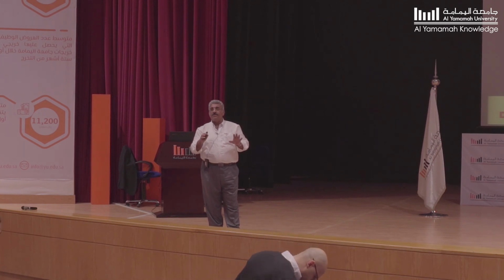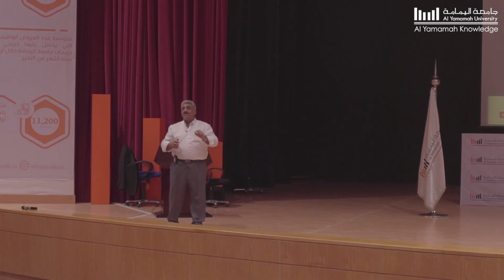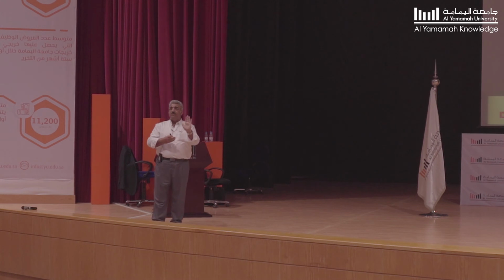Please, how do you deal with openings in terms of doors, and how do you block the fire there? You're talking about floors or doors, did I hear that right? Doors. Now for doors, you need to go to a special manufacturer; this is not the scope of work of Hilti. Every trade and segment in the market is 100% aware that there are fire-rated doors, so the door must be manufactured accordingly and certified by UL, showing that this type of door and this factory has passed UL. If you need 2, 3, or 4 hours of rating, they will provide you a door that fits 100%. Very good question. Others, please.